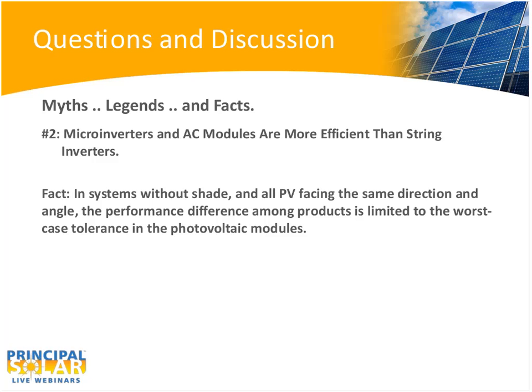None of them really have a clear-cut, this is the best for all applications. To me, I look at it in terms of physical system size, orientation, growth, and a number of other factors. There is no one perfect solution for every application. When you look at a residence, let's say you don't have space for all the PV to be mounted contiguously in one array. You want one complete large south-facing, well, some direction. They all need to be facing the same direction. If there is a marked difference between a pair of panels or several, now you're not going to get optimal output even connected to a string inverter. That's where AC modules or microinverters may come in.